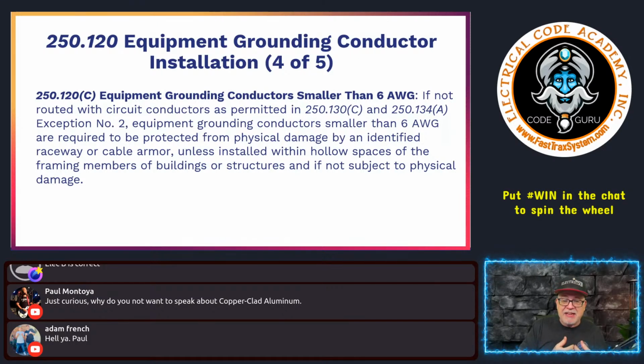But when I take that EGC from my panel to that box, that doesn't have an EGC in it, I've got to follow some rules. I've got to protect that conductor en route to that box, and I've got to use a wiring method. Generally, if it's subject to physical damage, which is subjective, then I've got to protect it. You know what I'm saying? So it's probably more trouble than it's worth. Most people just put a GFCI upstream and protect it, or a GFCI in the location, and just let it ride. But you do have options. So go check out 250.130(C). That's your homework to check out today when the show is over. Okay.